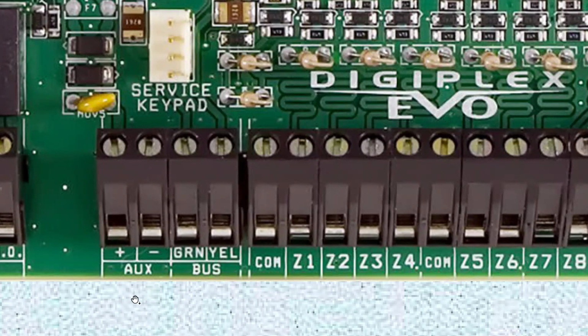Because ampacity is the ability to carry current by a conductor. But amperage is the ability to provide current by the power supply. So sometimes when you get too many motion sensors or too many whatever, it adds up. So not only do you have to read the ability for this to provide the current and still stay at the 12 volts that it is spec'd for.